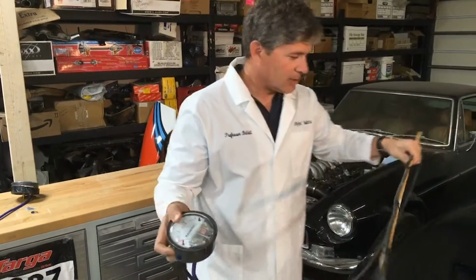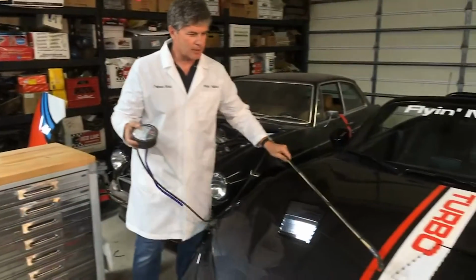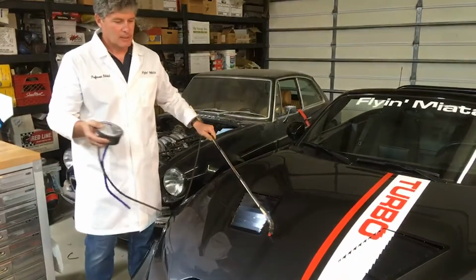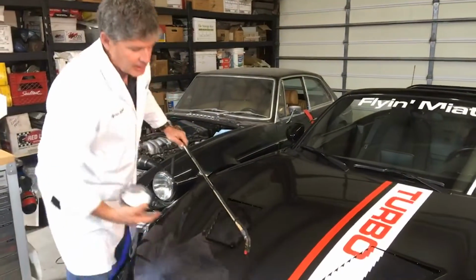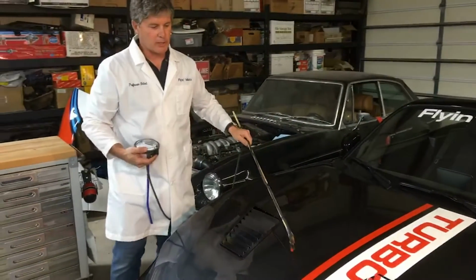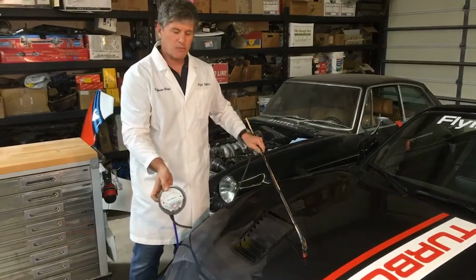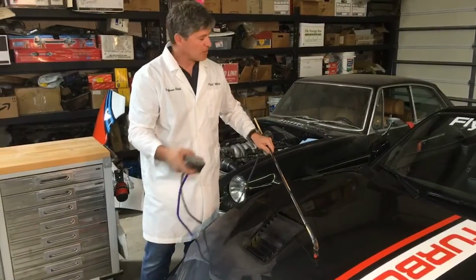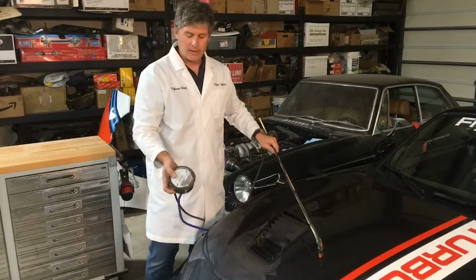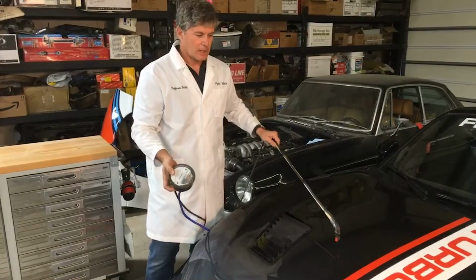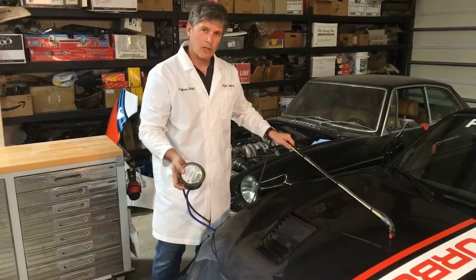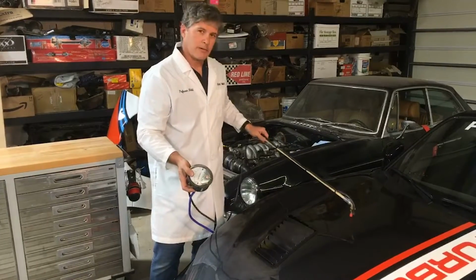What this does is let me put it at a specific point on the hood and measure the relative pressure right there. If the interior reference pressure isn't moving around, you'll get good deltas, and you can tell if it's a high pressure area or a low pressure area as you work your way around the hood.